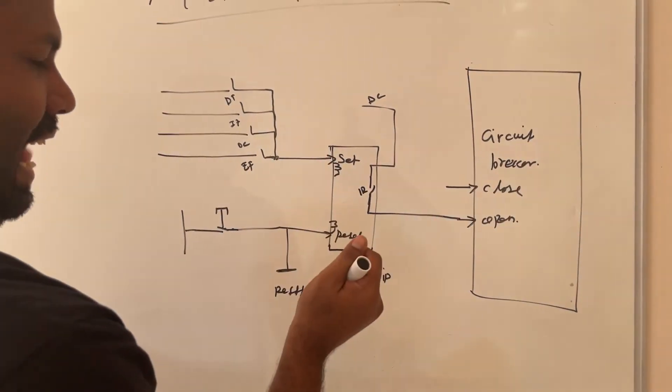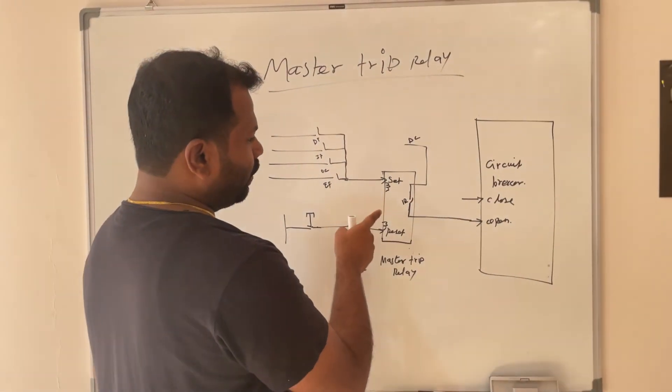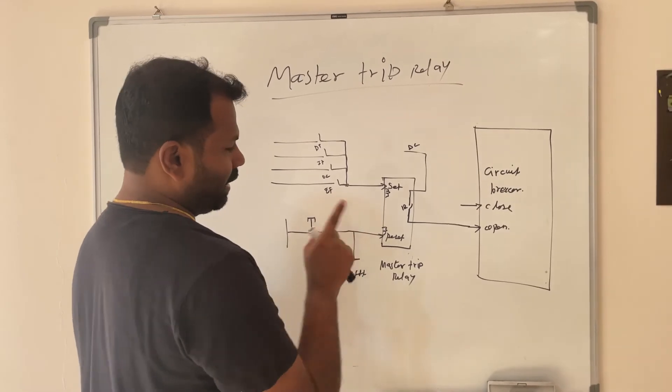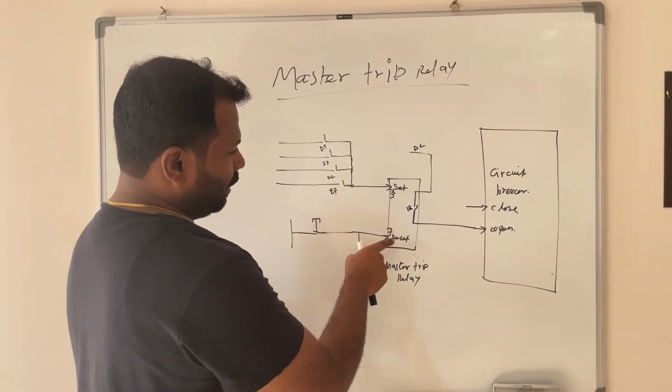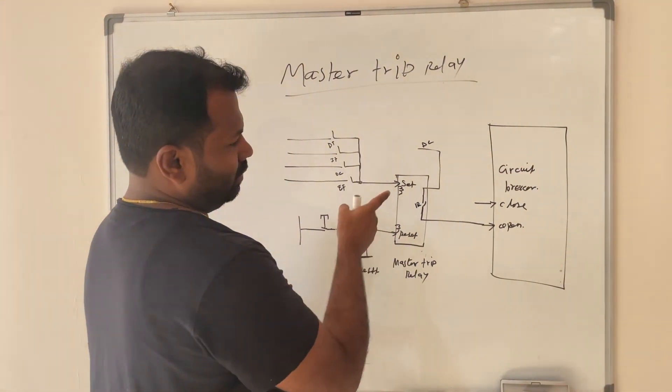This relay will work like a latch relay. Once this fault is activated and breaker is tripped, you have to reset manually or electrically by giving supply to reset coil, or mechanically you can reset the master trip relay. Unless you reset, the breaker will remain in open condition or trip condition.